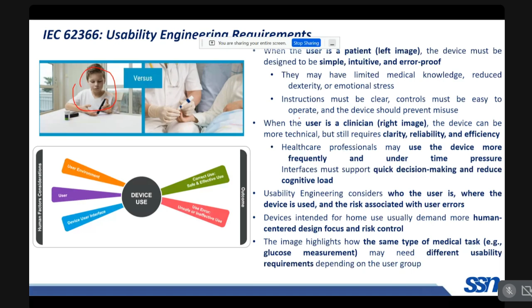And the standard for usability engineering is IEC 62366. In usability engineering, they do two things. One is called formative evaluation, and the other one is summative evaluation. Formative evaluation happens during the development of the product, and this could be done by means of questionnaires. Usually it is done on the prototype of the device, and it is iterative during the design and development of the medical device.